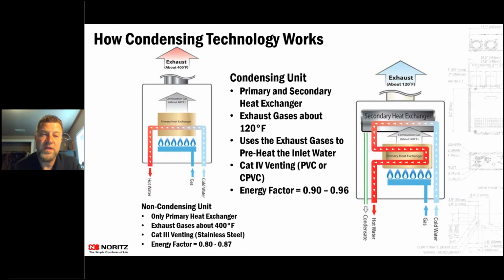Yeah, so basically from non-condensing to condensing, that condensing technology is taking the heat that's in that flue gas and preheating that water that's going through the secondary heat exchanger. So you're actually capturing more of that. Just like a high efficiency furnace, they're doing the same thing. They're taking that flue gas, which is preheating their coil, and so that's basically reusing that energy and taking that stack temperature down so they can vent in PVC as well.